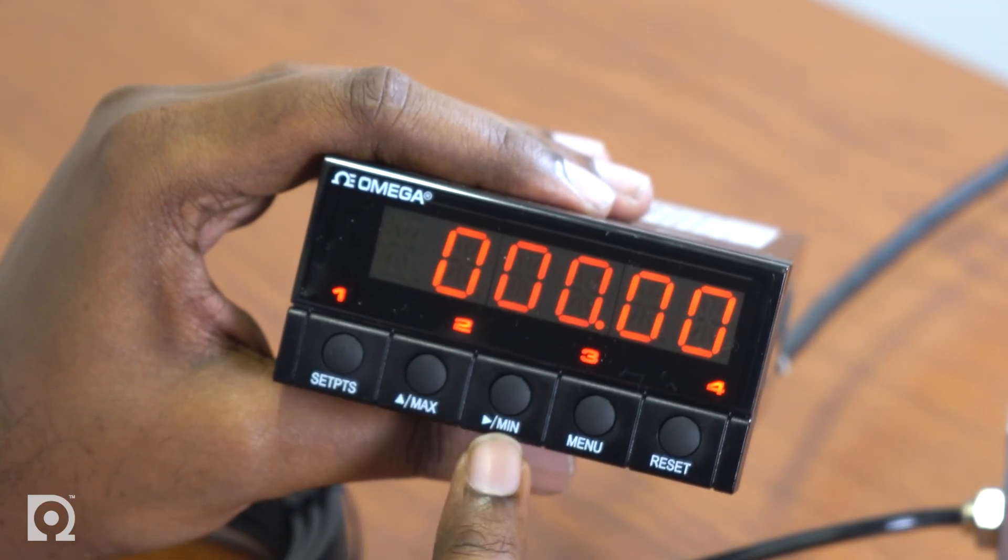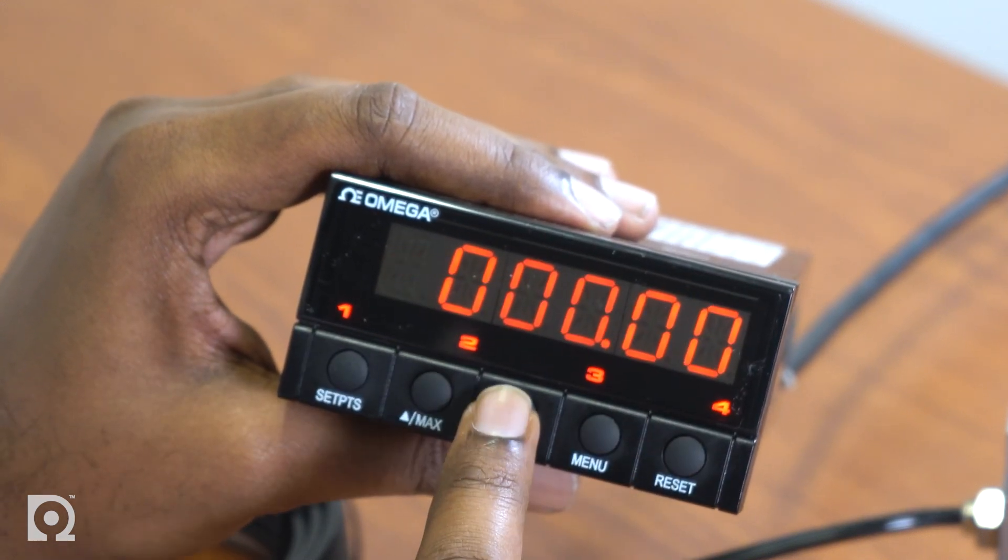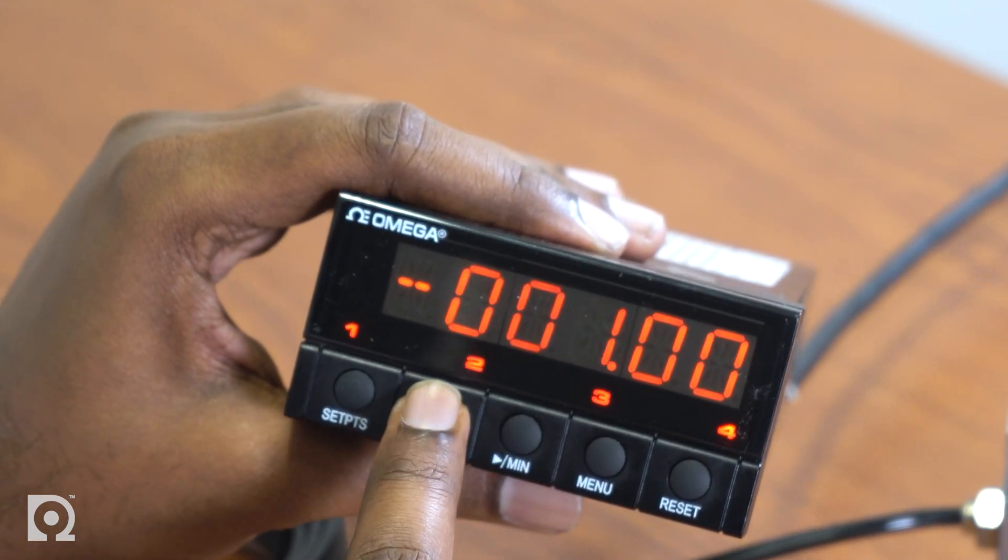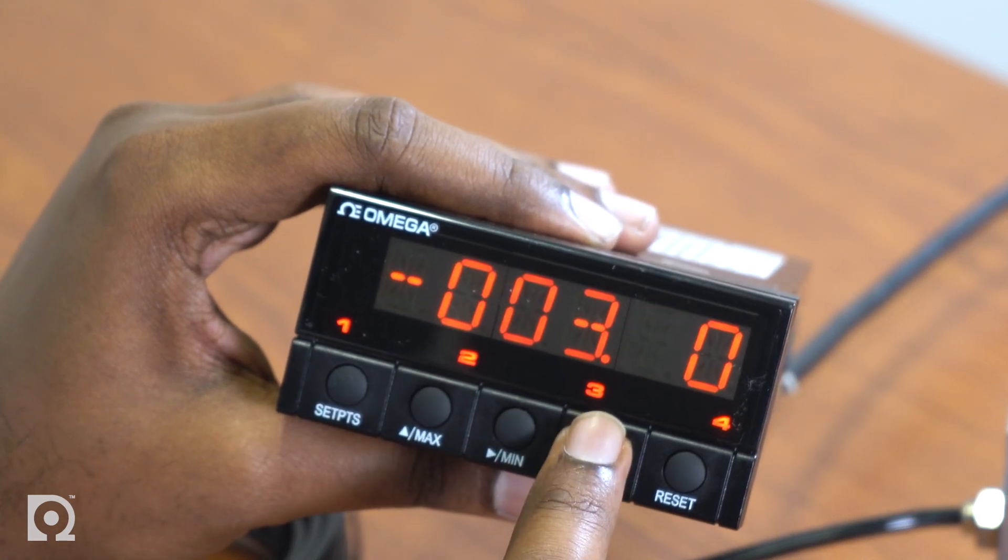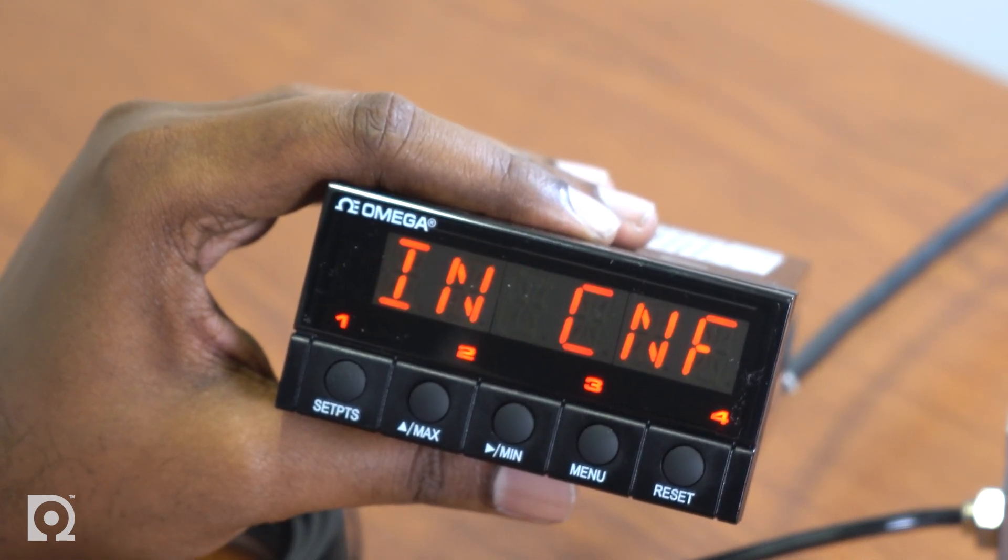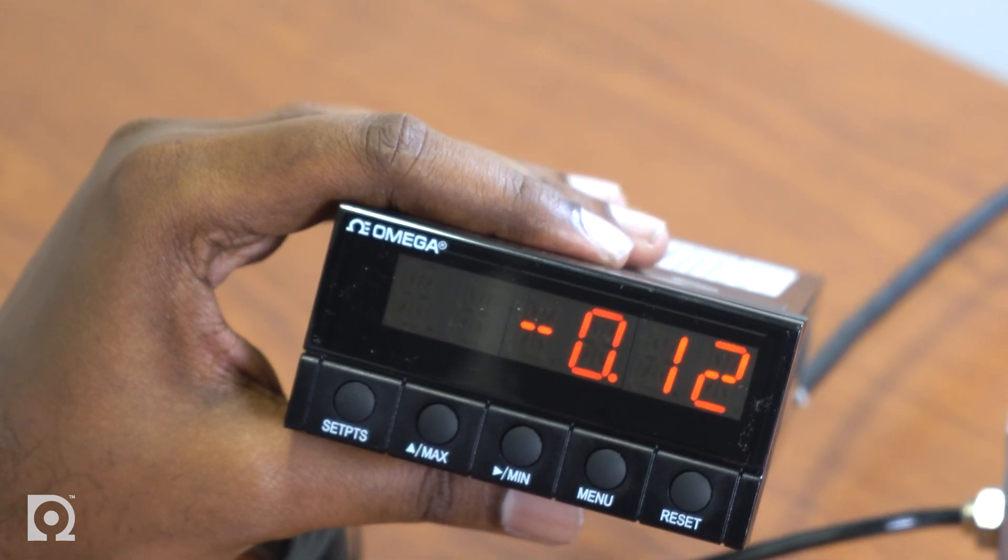So I'm going to put negative three point eight over here in RDG OF. Press the min button to scroll through the digits. Use the max button to change the value of the digit. So I'm going to set it to minus three point eight. Press the menu button to store it. It'll flash stored. Press the reset button twice to go back to run mode.